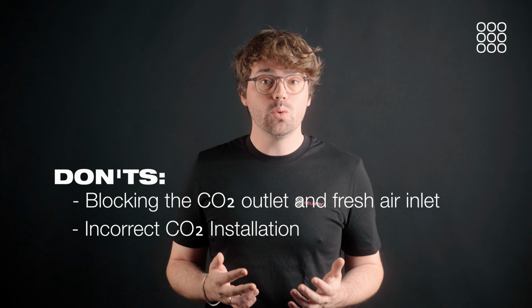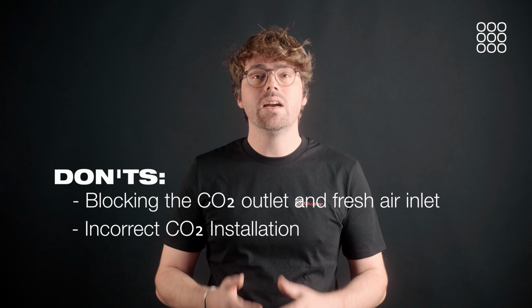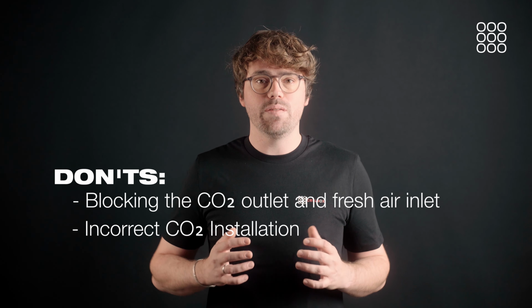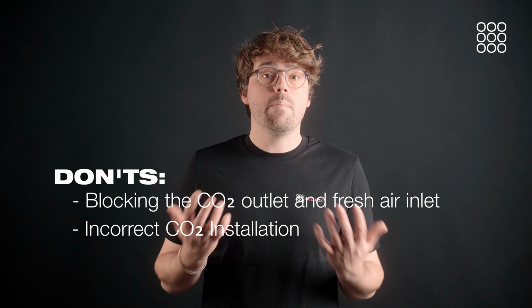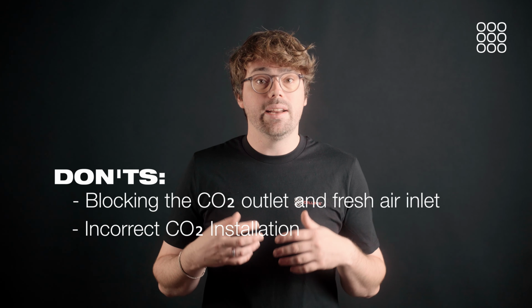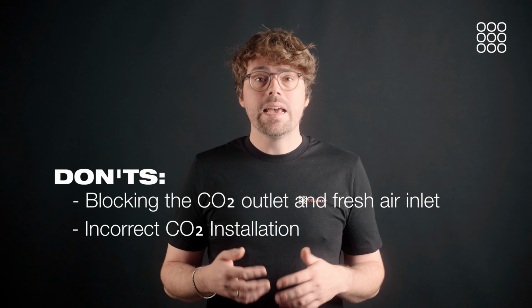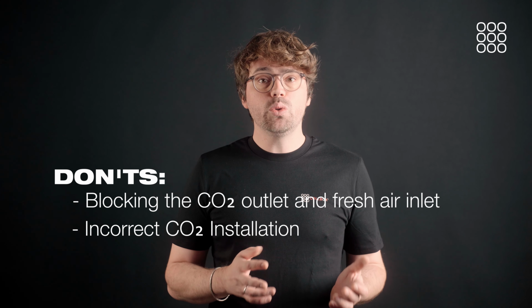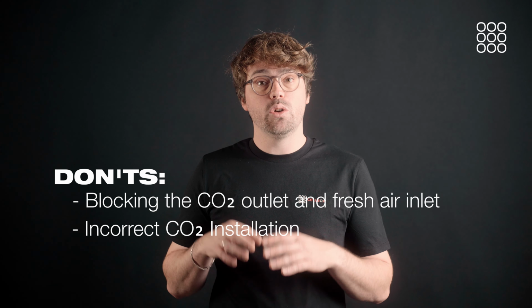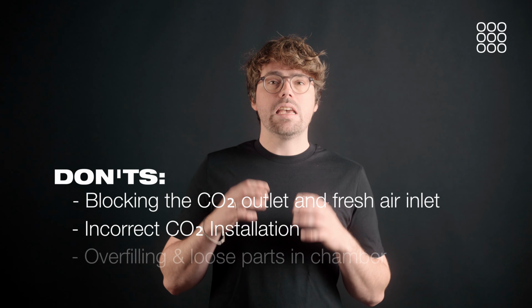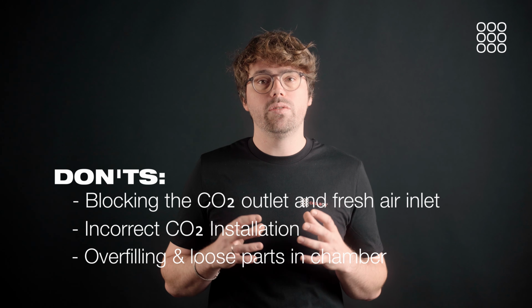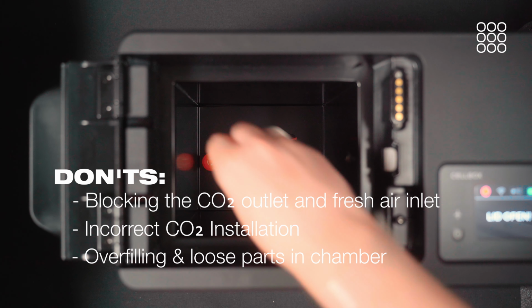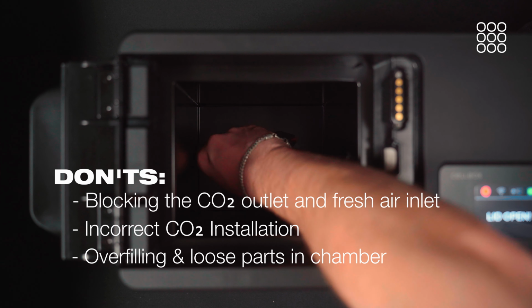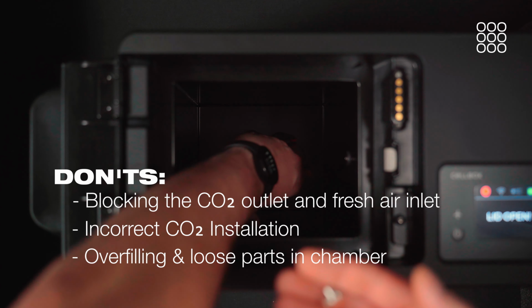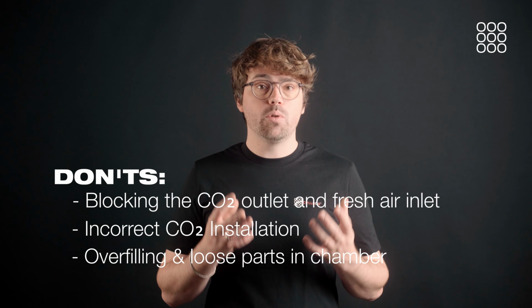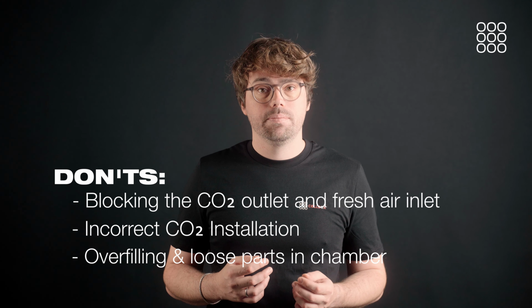When replacing the CO₂ cartridge or inserting the dry ice container, ensure that both are securely and fully fastened. A loose CO₂ cartridge may result in lower run times, while an improperly inserted dry ice container can cause CO₂ overshooting due to uncontrolled release of gas into the internal environment of the Cellbox Go. Avoid placing loose parts or overfilling the chamber with materials that could interfere with the device operations. Loose items could damage the internal fans or disturb airflow, compromising the transport environment.